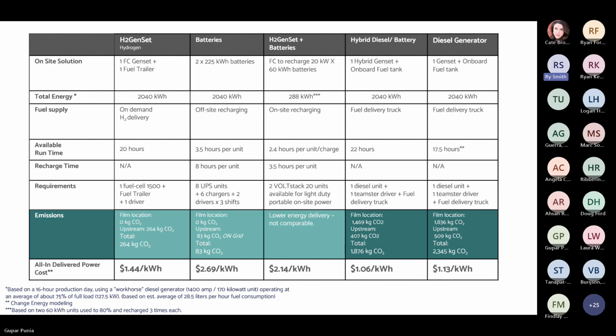If you were to hybridize the hydrogen genset with batteries so you don't have to take the batteries back, keep in mind we're looking at a low carbon intensity operation. Rather than charging the batteries from a diesel genset, the batteries would have to be transported back to a point where they can be recharged, and that cost was built in. If you don't have to do that, that's what the third column is all about.